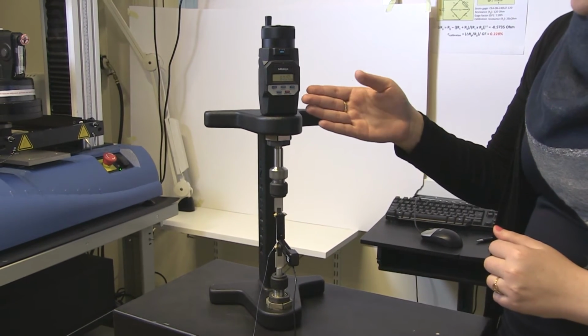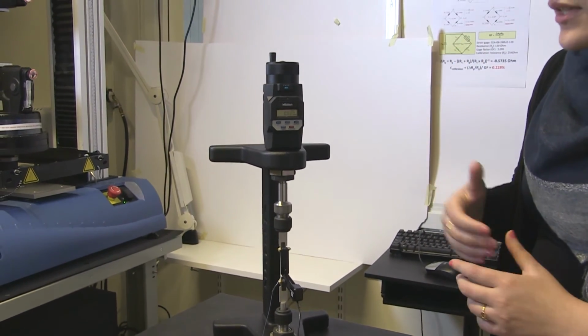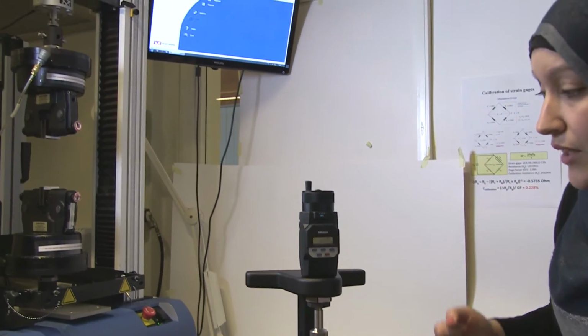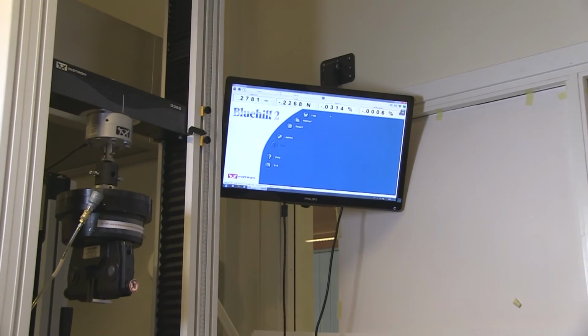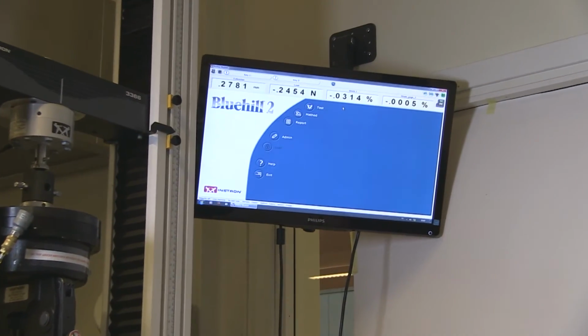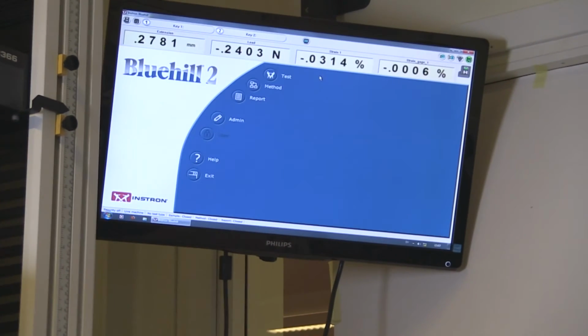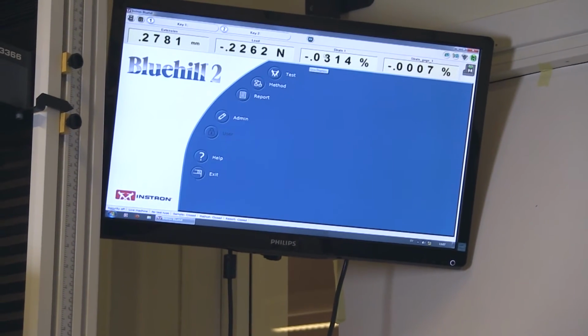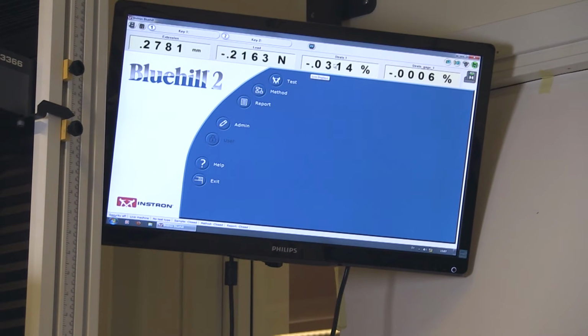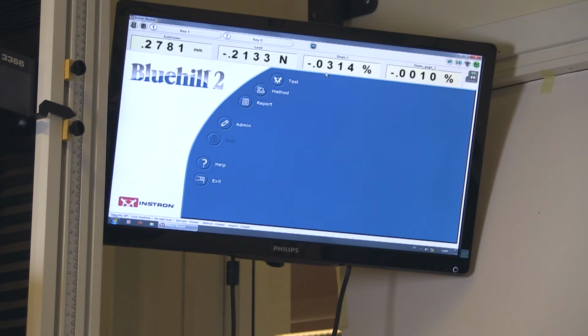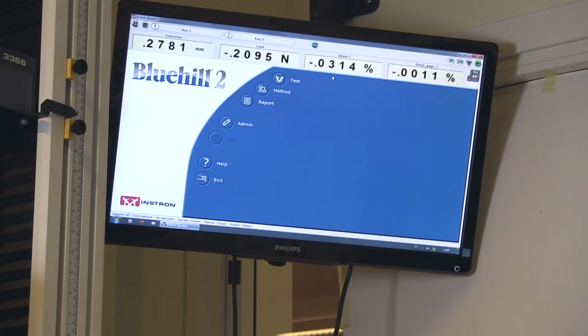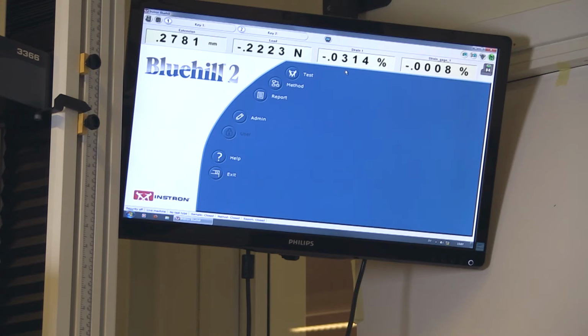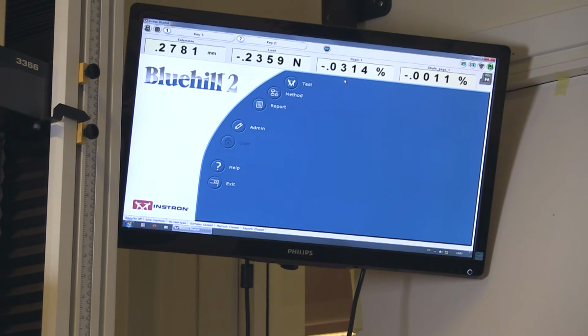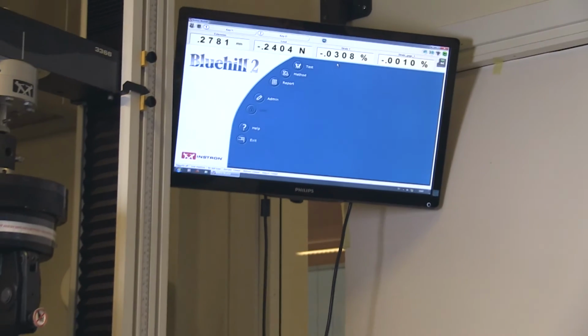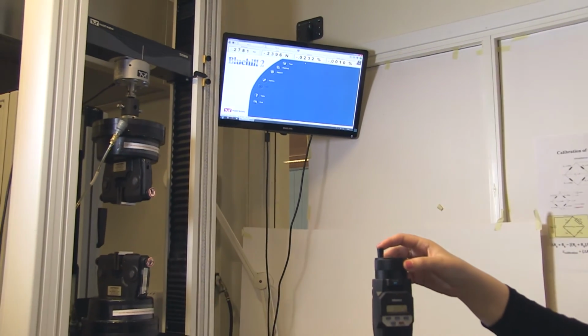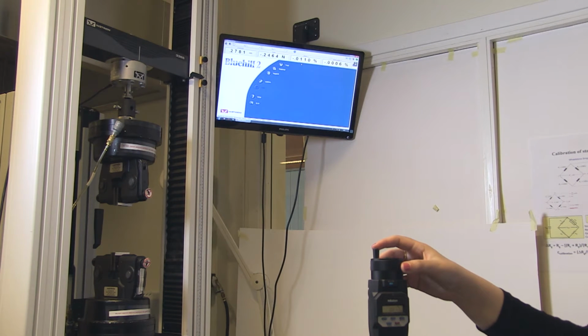Now we have 0, and let's look at the screen to see which displacement we have. But before that, we should remove the pin, of course, when we start the calibration. And on the screen you can read here, in the second value from the right, the strain value that we are measuring from the extensometer, which is not 0 in this case. So we have to bring it to 0 by moving the micrometer. We should move it carefully in one direction.